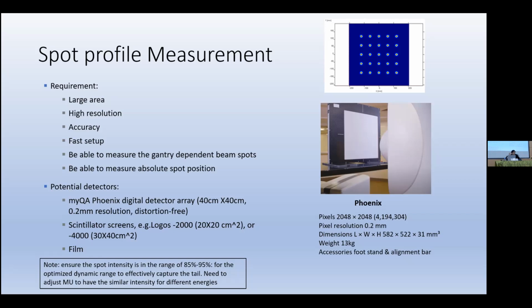Some systems, depending on how much dose you're actually delivering, whether it's going to be a heavy spot, let's say something that has 10 to the 8th protons in it, or a light spot, something that has maybe only 10 to the 6th protons. So that's two orders of magnitude difference at the core versus at the tail. Can the detector you have also handle that dynamic range? Because the spot characteristics when you're doing a large heavyweight spot may be different than when you're doing a smaller lightweight spot. So knowing that there is a difference, that your system will operate differently under those two characteristics, is different from knowing if your detector can actually measure based on those characteristics.